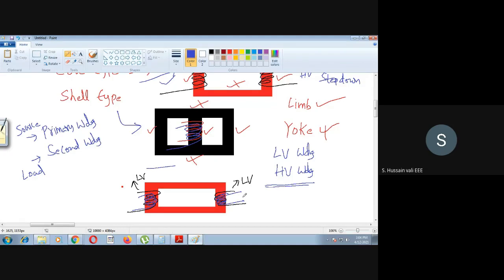This is important because the LV winding has less voltage, so when you put it directly on the magnetic core, you don't require much insulation between the LV winding and the magnetic core. Whereas you always put the HV winding above the LV winding.